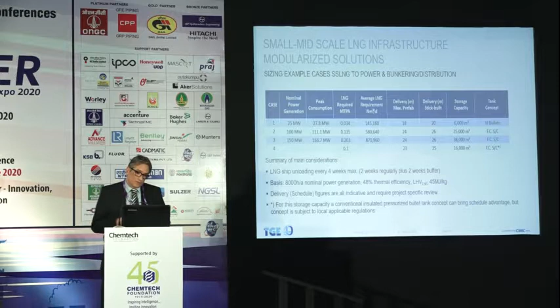Very small ranges in the range of 25 megawatts, we only need storage capacity of 6,000. There we are still with vacuum insulated bullets. If we go higher, we usually would go for the atmospheric storage tanks.